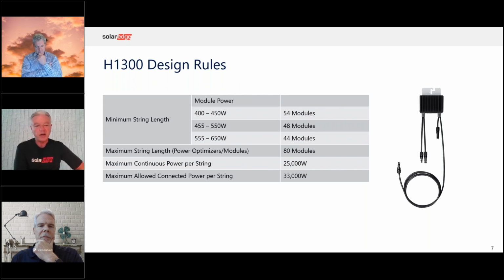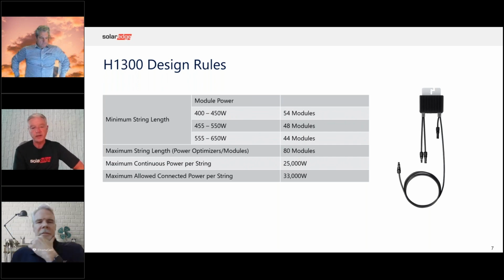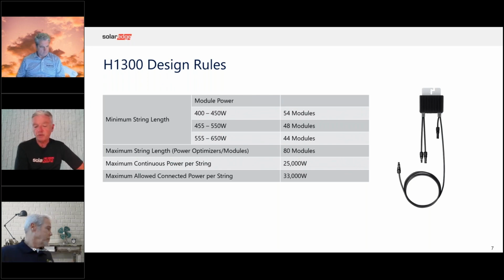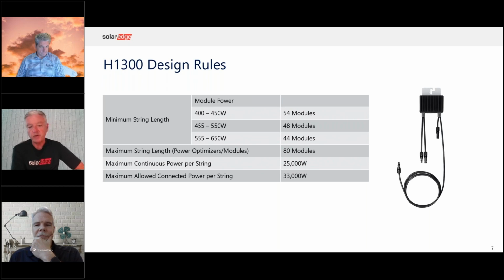So here you see the design rules. Minimum string length, depending on the power class, is either 44, 48, or 54. And then the maximum is 80, depending on the amount of power you have connected. And so the nominal amount of power that you would connect is about 25 kilowatts, 25,000 watts, but you're allowed to oversize it up to 33 kilowatts. So that's significantly more than you can get on a string with a normal 1500 volt string inverter that you see in the market today.